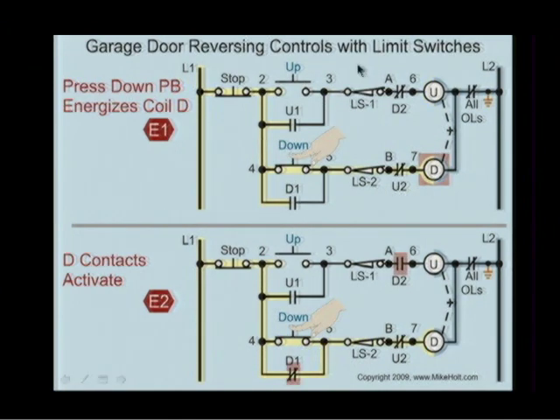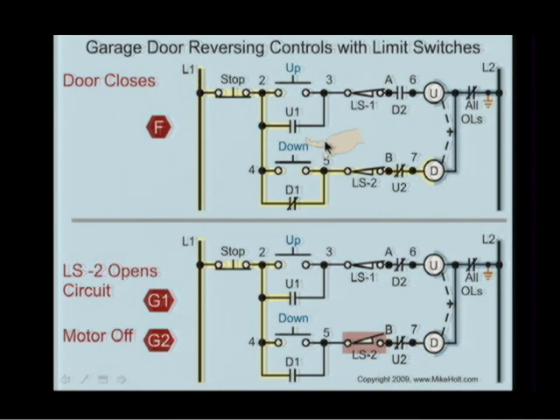All right, let's now press the down button, energize the down coil because limit switch 2 is closed. And then press the down button, close the down contact 1, open up the closed contact D2, release the button. I'm able to maintain voltage to the down contact, so the motor is now going in the direction to go down. And once it gets to the end of travel, it has a limit switch that opens it, and now the door is down.